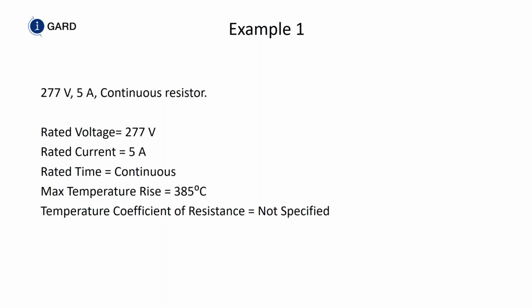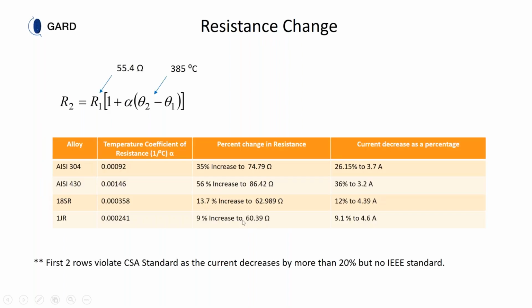We're going to take an example of a high resistance grounded system, 480 volt system. We're going to limit the fault current to 5 amps, continuously rated, 385 degrees C temperature rise as far as IEEE is concerned, 375 degrees C rise as far as CSA is concerned. So here are some typical materials being used in the industry: 304 stainless steel, 430 stainless steel, 185R, and 1 JR. And they have low temperature coefficient of resistance. And these are publicized, and you can get them by the mil spec. Well, when you do the test and you go through the math, 55 ohms, alpha is substituted with this number right here, and the temperature rise, 385. This is the temperature rise because you know the ambient, you know the maximum temperature.